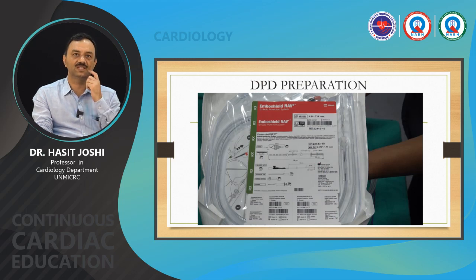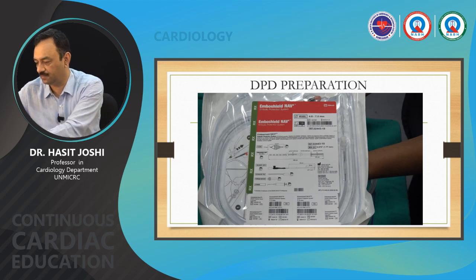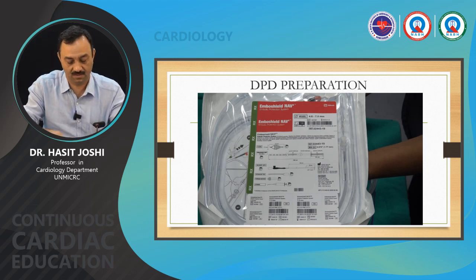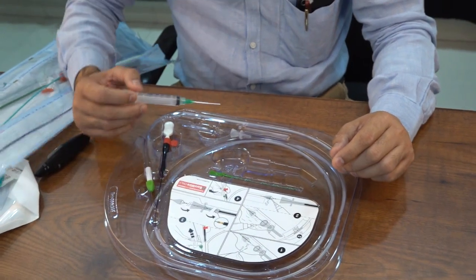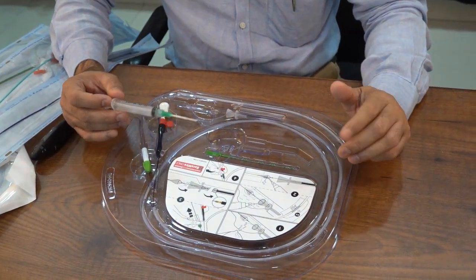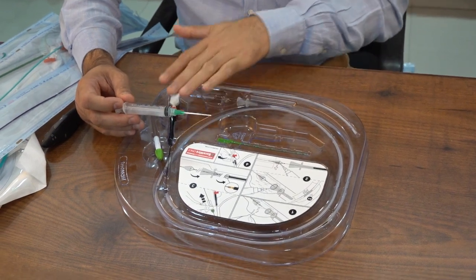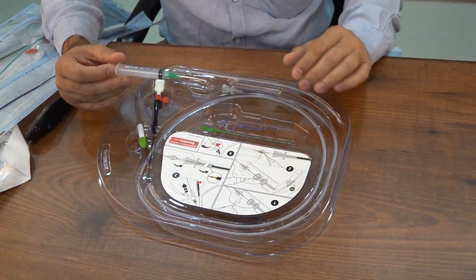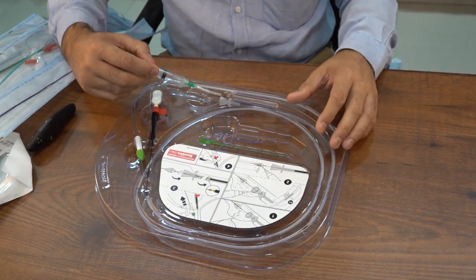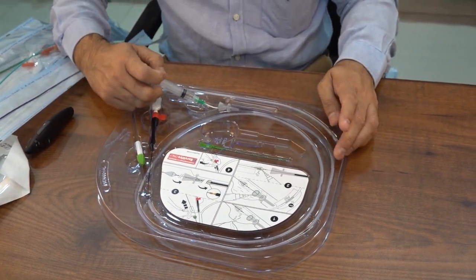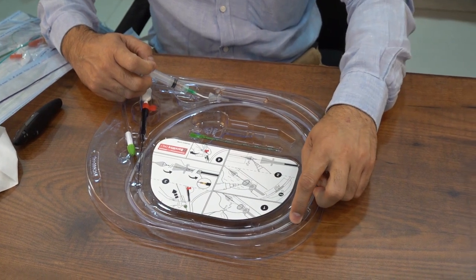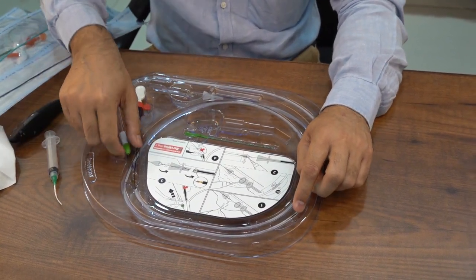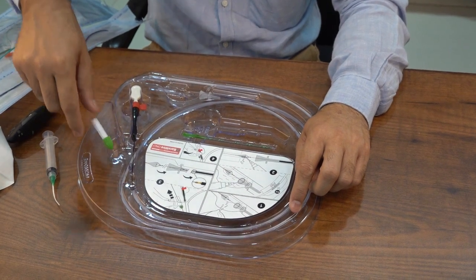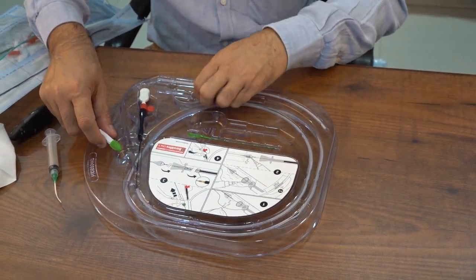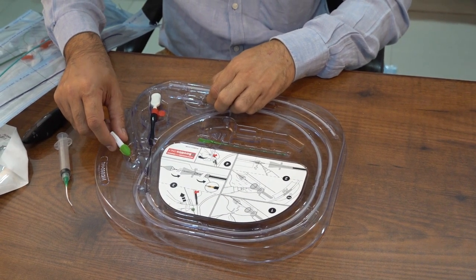Okay, so this is the Emboshield. Can you focus over here? So this is the video. You can see the video also. Fill all the chambers with saline. Fill this syringe with saline and flush this from here till all air comes out. Then this is the wire on which the Emboshield is mounted, you can see, right?